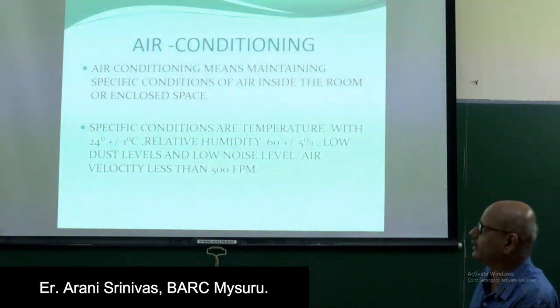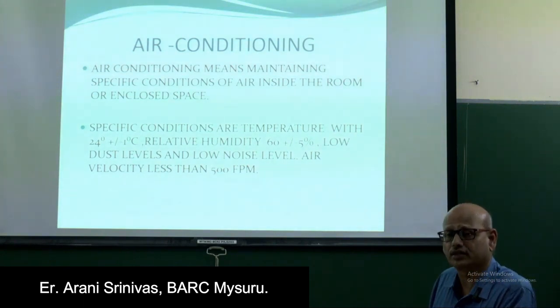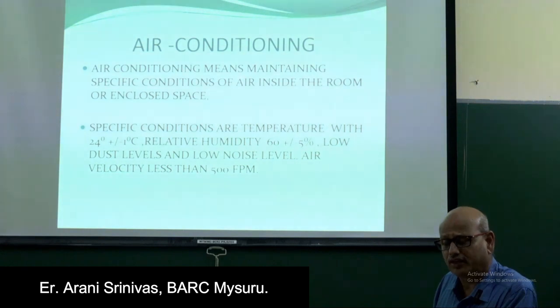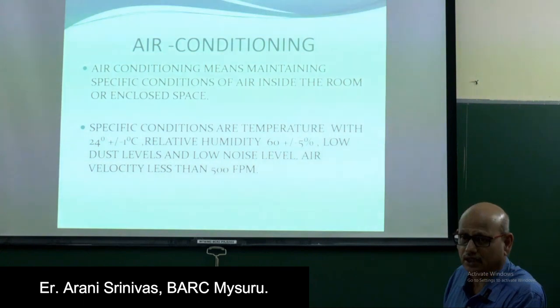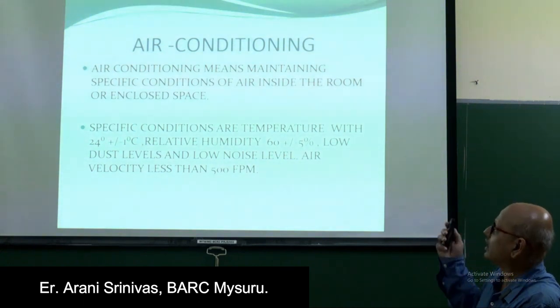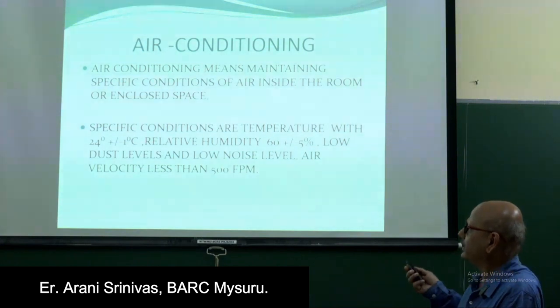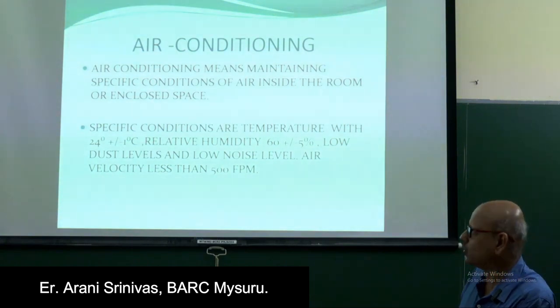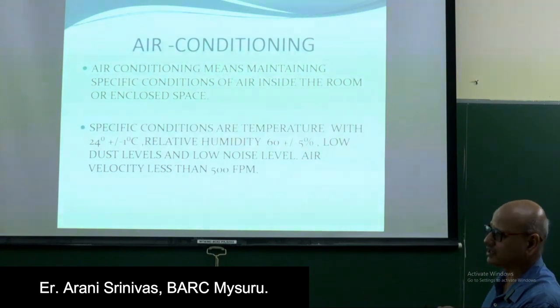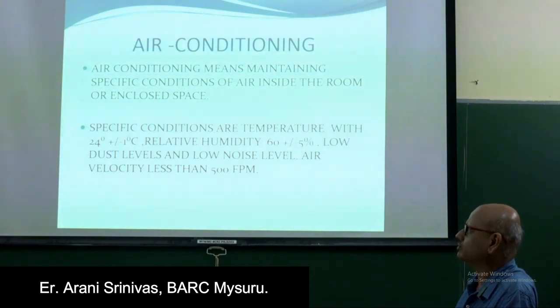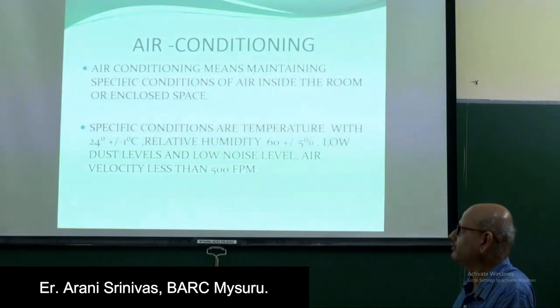Now, air conditioning. What is the difference between refrigeration and air conditioning? Refrigeration is only removal of heat from one space and throwing it out to the outside. Whereas in air conditioning, we have to maintain some specific conditions: temperature should be 24 plus or minus 1, relative humidity 60 plus or minus 5%, then low dust value, low noise level, and air velocity should be less than 500 fpm, that is feet per minute.